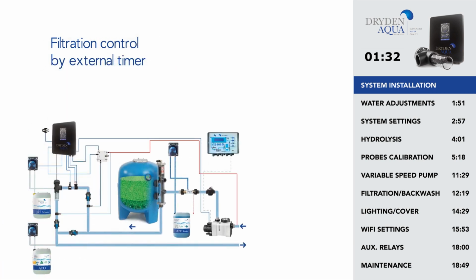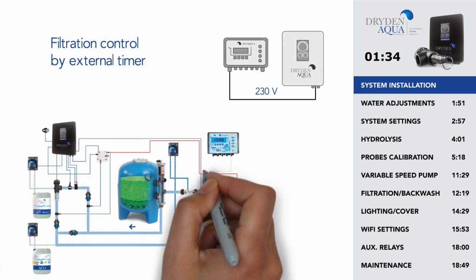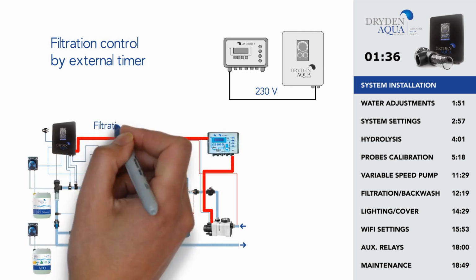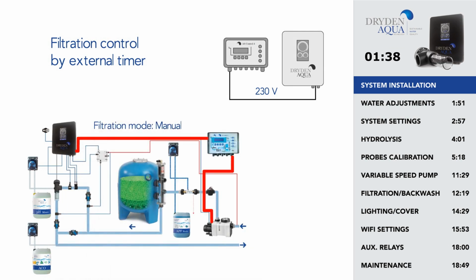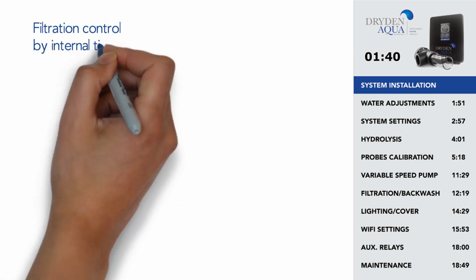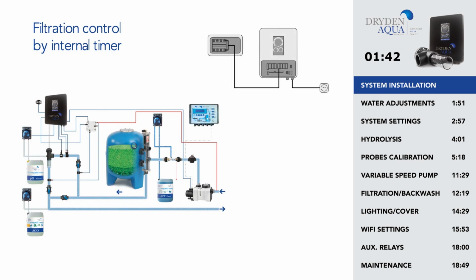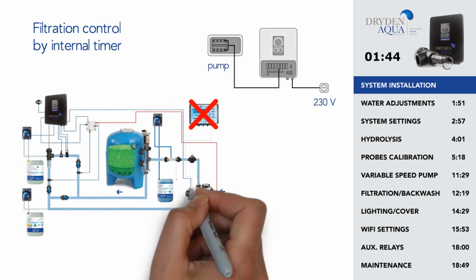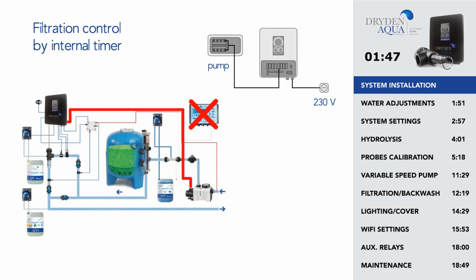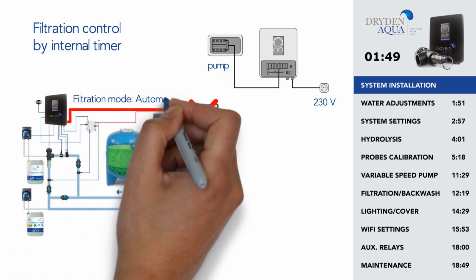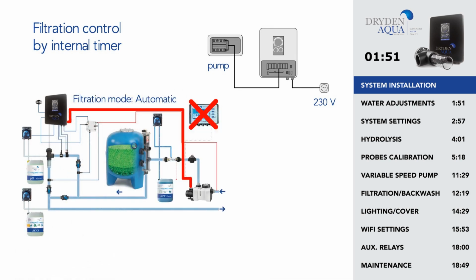You will be able to control filtration either with an external timer. In that case, filtration mode is set on manual in the DA-Gen. Or to control filtration directly with the DA-Gen internal timer. In that case, the filtration pump is connected directly to the DA-Gen and filtration mode is set on automatic.